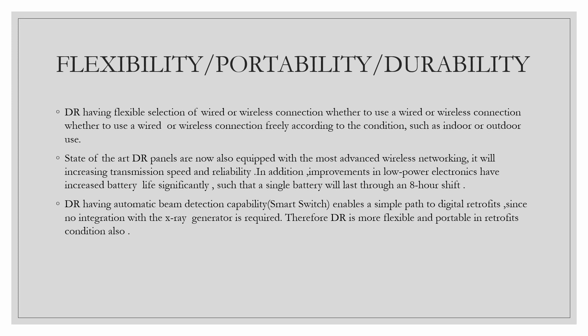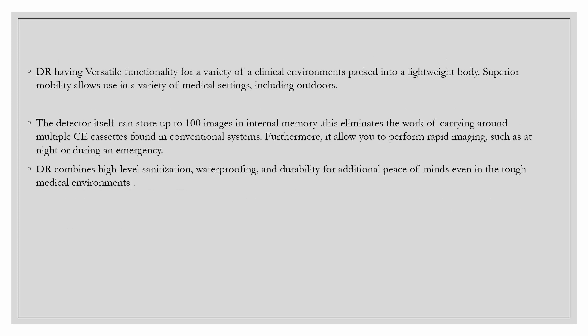DR has an automatic beam detection capability — a smart switch — which enables a simple analog-to-digital retrofit. The panel can be used in retrofit condition because there is no required integration with the X-ray generator, making DR more flexible and portable in retrofit environments.